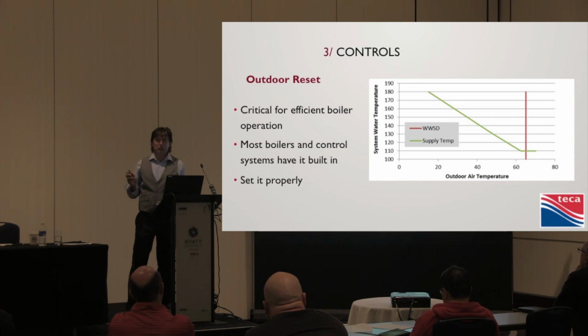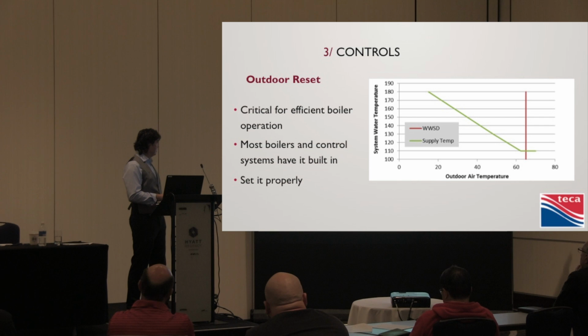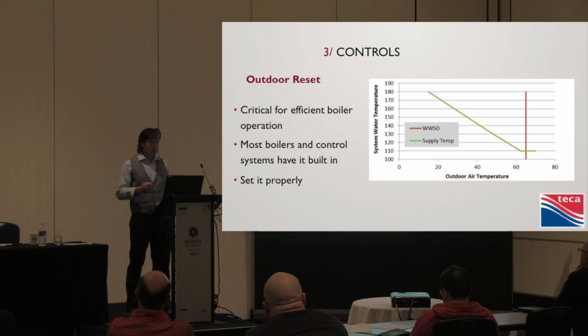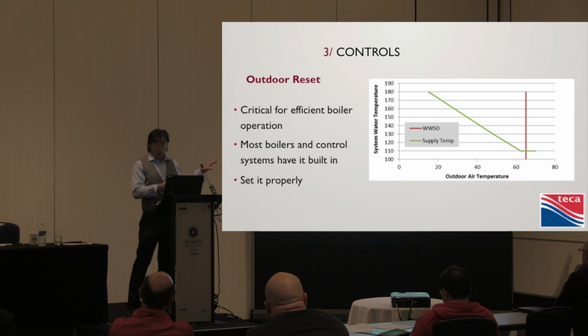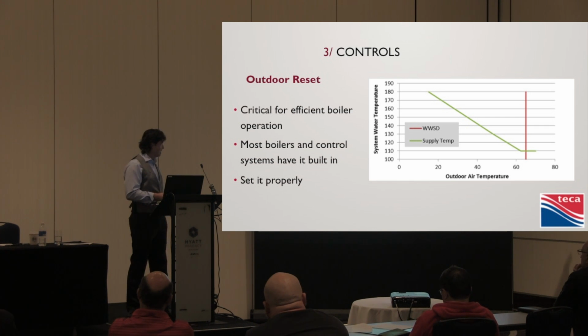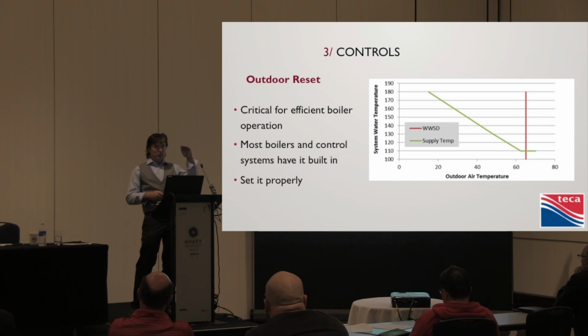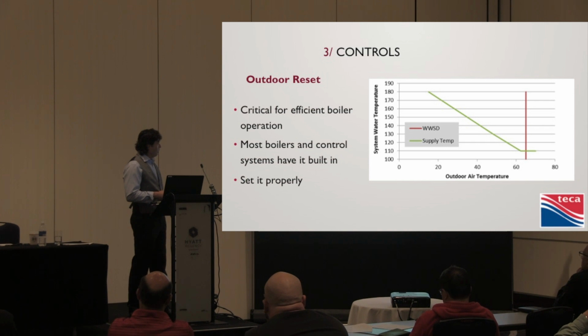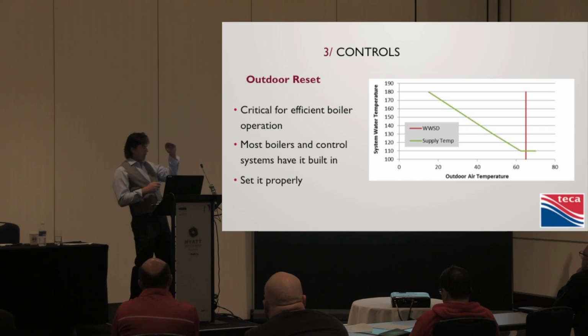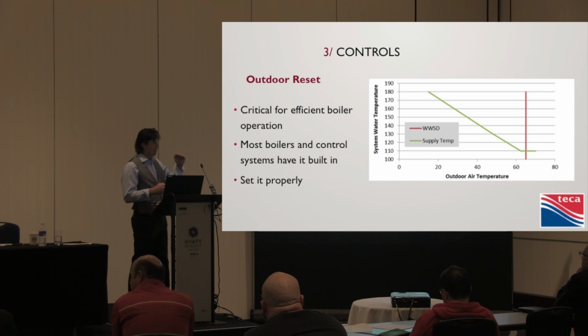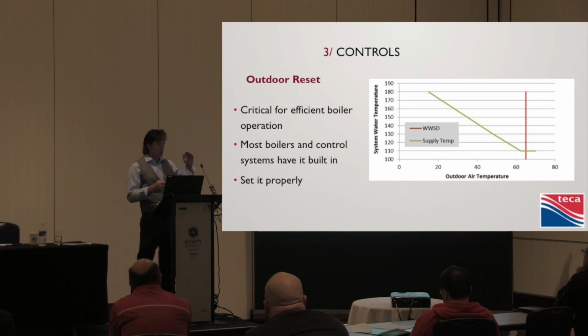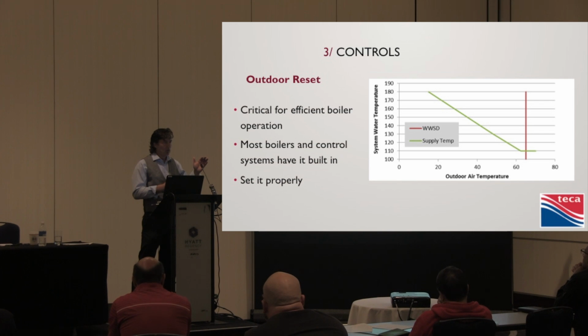I'll just talk about warm weather shutdown quickly here. It's pretty critical. All these condensing boilers that we're talking about, even that heat pump has warm weather shutdown included in it. So have your contractor dial these things in. It's a big deal. So if we think about our efficient operation, we know our boiler modulates to meet the heat load requirement. So the flame will modulate. The BTUs will modulate to heat the requirement that it knows it has. So what is the requirement?